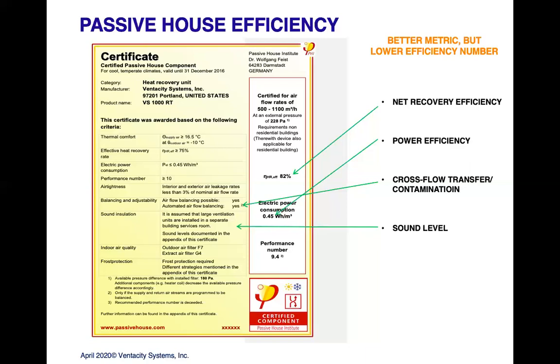Crossflow contamination, the second one up. This is the transfer of exhaust air that you're trying to leave the building to the incoming airstream, and crossflow contamination is really high on people's minds right now when we're talking about a pandemic with viruses. It's a really important factor when you don't want to transfer the outgoing air that you're pulling out of a building that potentially has people that are infected to the fresh incoming air that then gets distributed into the building. So I really want to stress that.